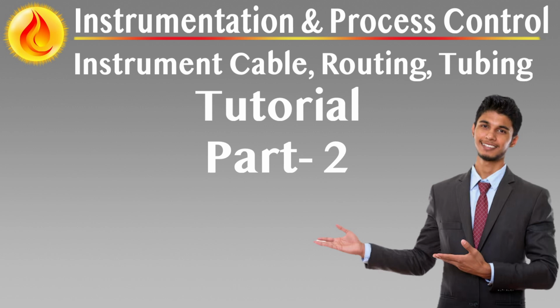Effective cable routing integrates structural availability, physical protection, fire zone avoidance, and maintenance accessibility. Single-core signal cables are routed from field devices to junction boxes via dedicated supports such as trays, trunking, steel angles, or beams. Conduits are not recommended due to their limitations in ventilation, accessibility, and thermal expansion. Above-ground routing must avoid interference with equipment access points, high-temperature surfaces, sample stations, and drain or vent lines. Routing near earthed steel structures or piping is encouraged to reduce electromagnetic exposure and enhance shielding effectiveness.